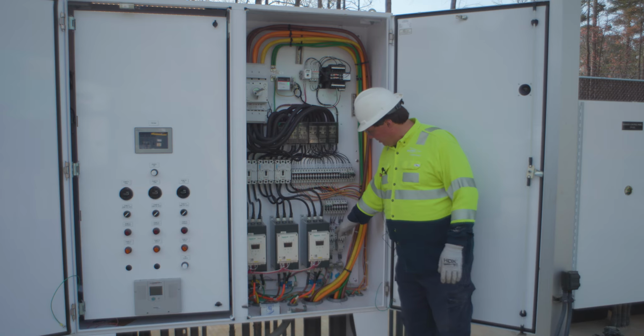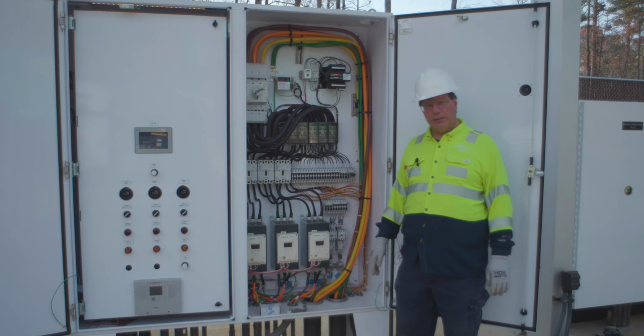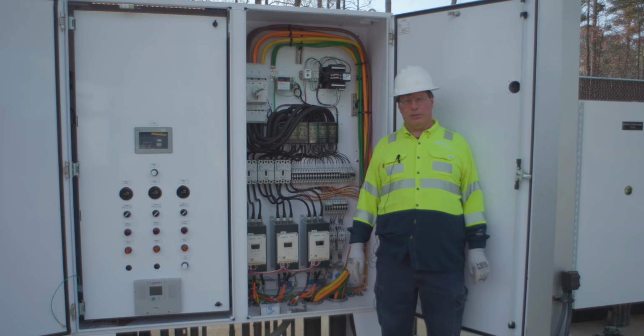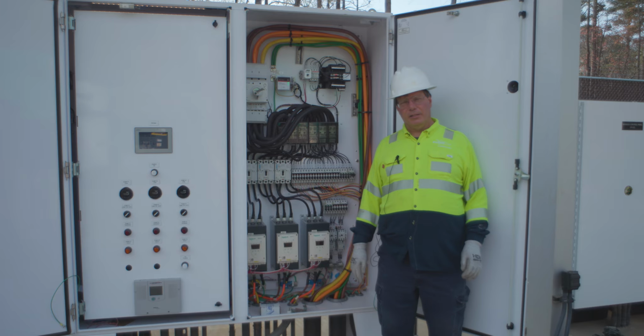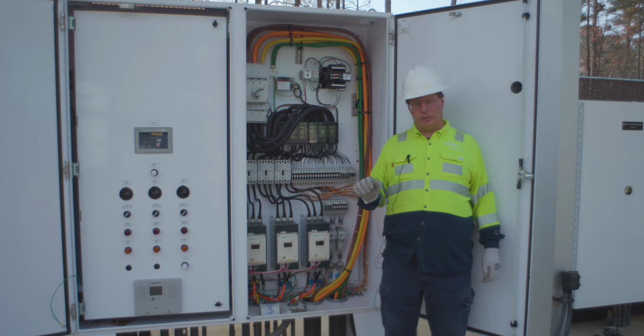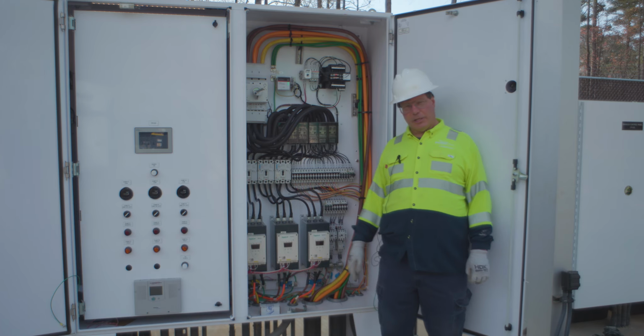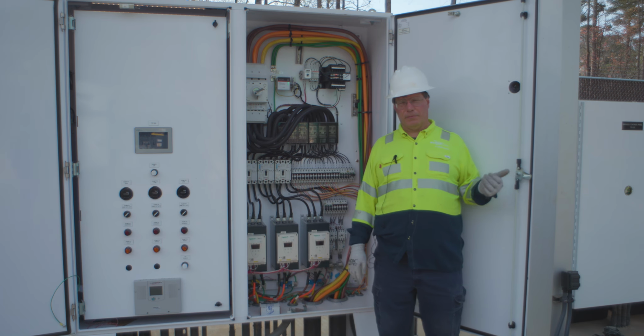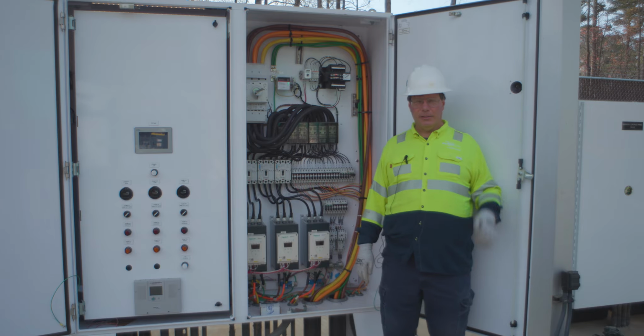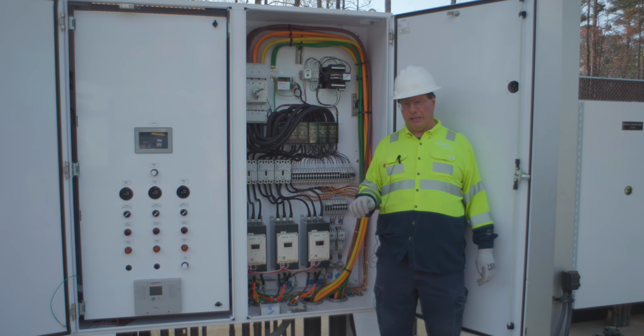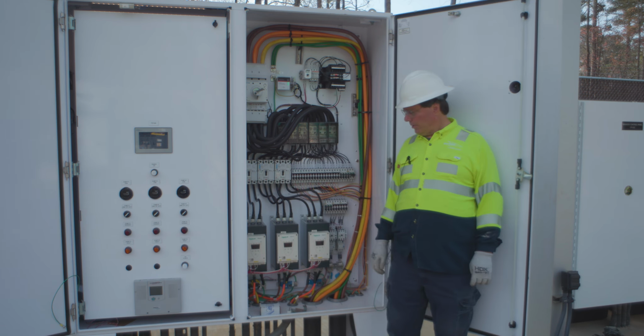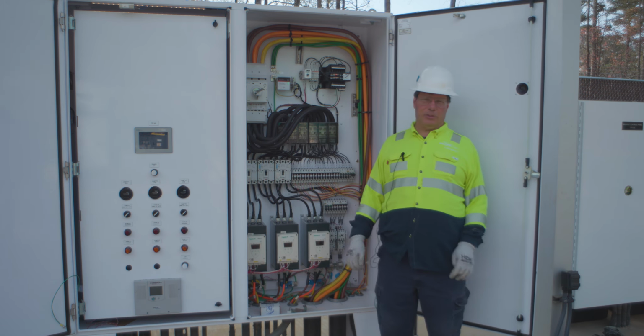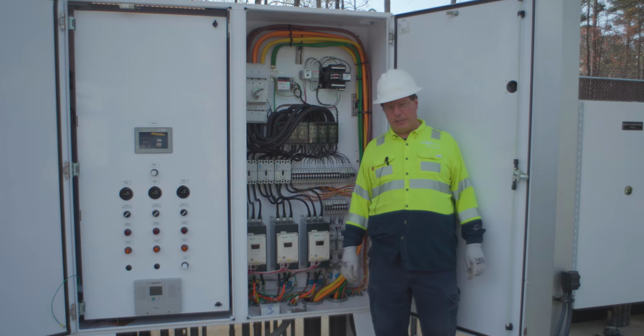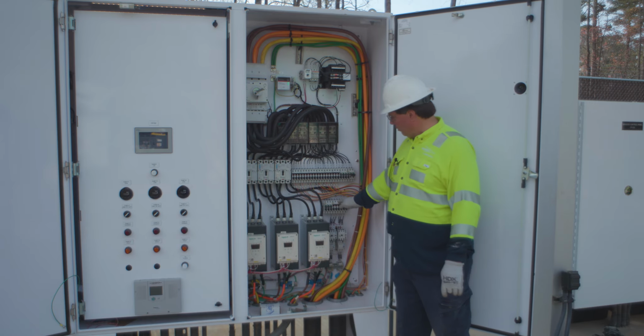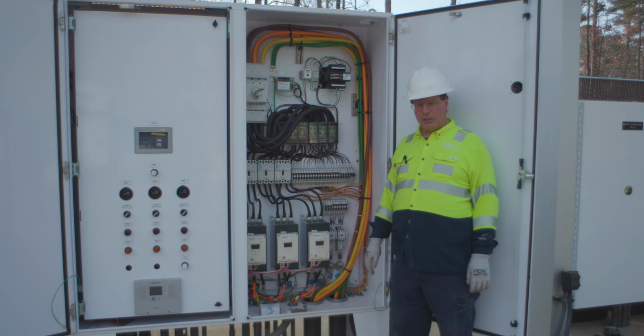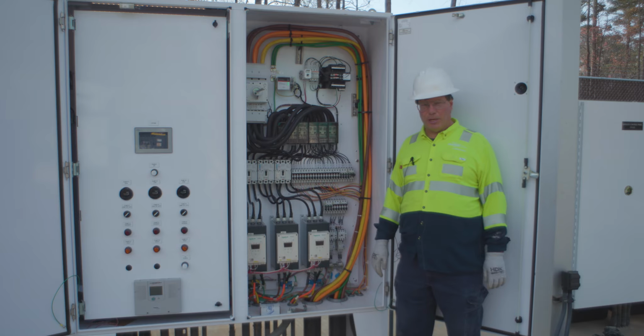On the side here, there's two small motor contactors. Those are the motor contactors that are connected to those 480 volt plugs we talked about at the storage tank. So when you turn that switch to on, it closes these motor contactors and allows the fans that you have connected to them to turn on. The switch to turn on those fans is over at those plugs, so that the person operating it can see the position of the switch and tell whether it's on or not before they plug into it. Each one of these has its own breaker, so if they had to do any work on that circuit, they could de-energize the breaker prior to doing the work.